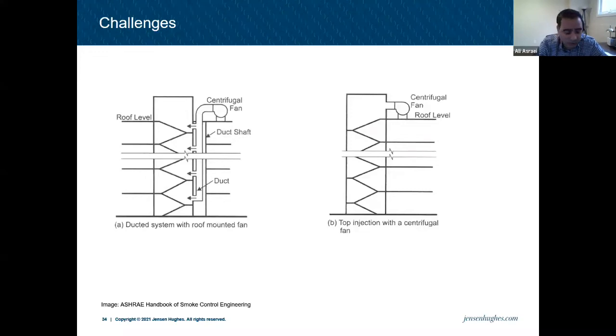What are the challenges? One of the challenges with smoke control systems is mostly for existing buildings that are not sprinklered. Let's say there's a fan here. This is a typical design on the right, like B, top injection. The fan is at the top of the stair, and the size of this fan depends on the number of floors it's serving.